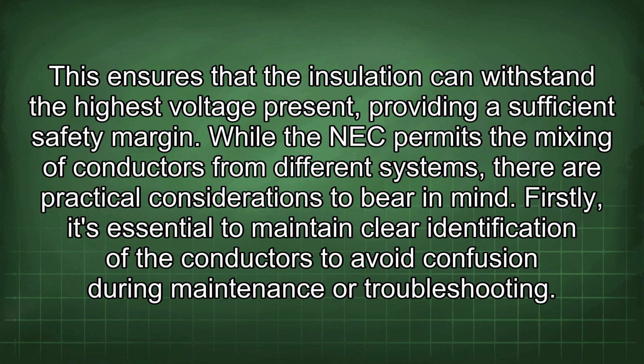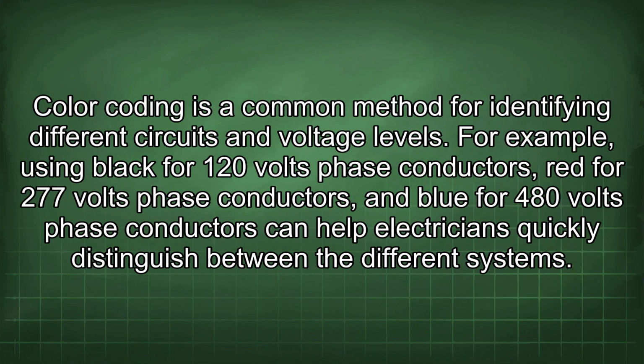While the NEC permits the mixing of conductors from different systems, there are practical considerations to bear in mind. Firstly, it's essential to maintain clear identification of the conductors to avoid confusion during maintenance or troubleshooting. Color coding is a common method for identifying different circuits and voltage levels. For example, using black for 120 volts phase conductors, red for 277 volts phase conductors, and blue for 480 volts phase conductors can help electricians quickly distinguish between the different systems.